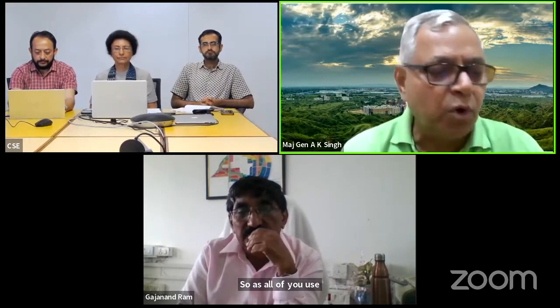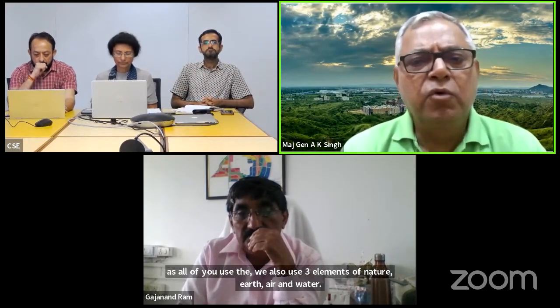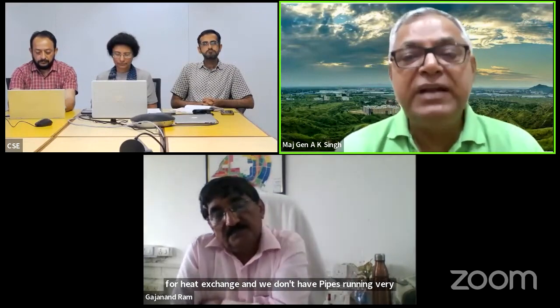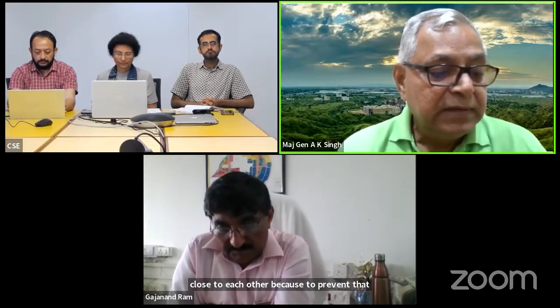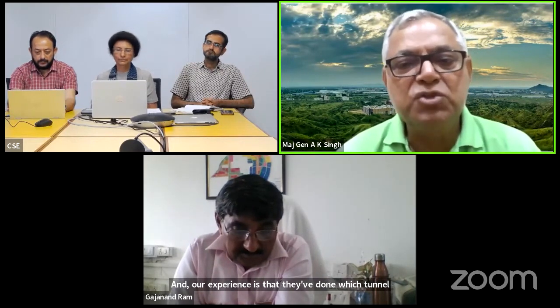So like all of you, we also use the 3 elements of nature: earth, air, and water. Our Hume pipes are at 4 meters depth, and we run them 100 meters for heat exchange. We don't have pipes running very close to each other, to prevent the interference that was talked about. Our experience is that the tunnel which delivers 25 degrees from October to April reaches 27 to 28 degrees in peak summer - that's the temperature delivered inside the tunnel.